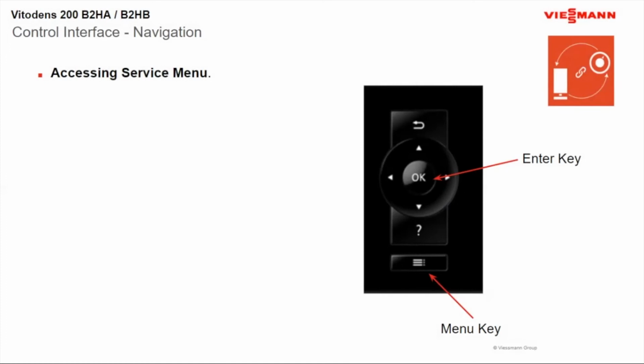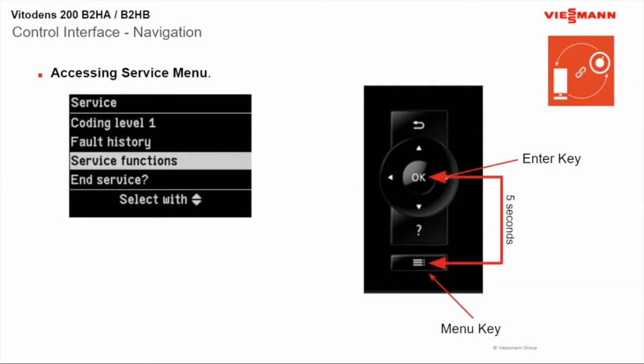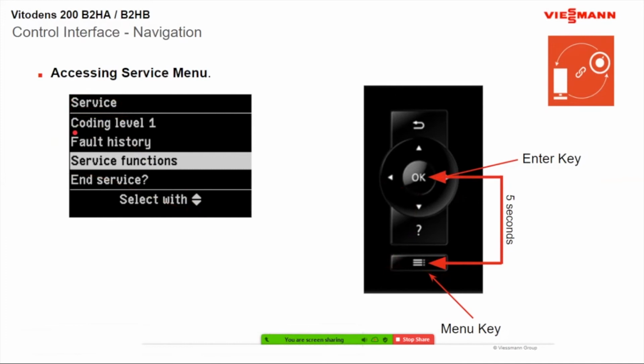To access the service menu, I find this is a very helpful one to know, because here you can see all your actuals, set points, your fault history, and service functions. So let's talk about that a little bit. All we're going to do is press OK and the menu key, both these buttons here, at the same time for about 5 seconds. You'll then see the screen come up, and it will say service at the very top. You'll find that most of your coding changes are done in coding level 2. Here's where you'll be able to see your fault history, service functions, and then end services, just to get out of the screen.